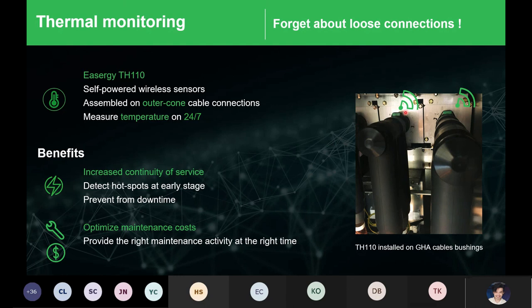They use a ZigBee transmission, 2.4 gigahertz. It sends the signal into a gateway. Literally all the joints within the switch gears, cable joints, or even for the transformer, we can actually install these TH110 sensors, and then you transmit the information of any hotspots to the gateway.